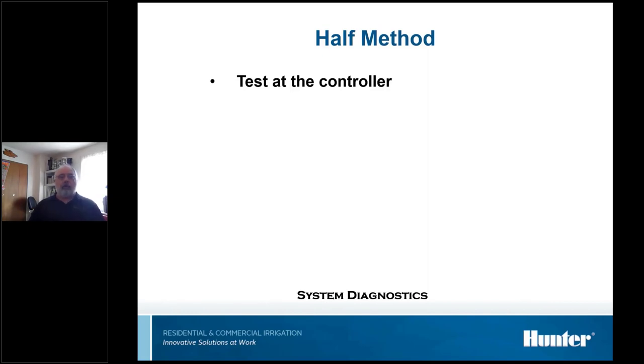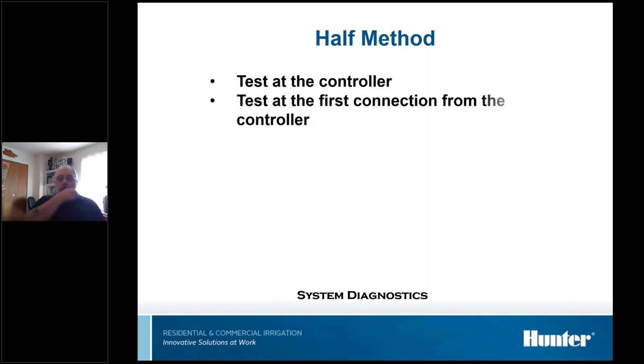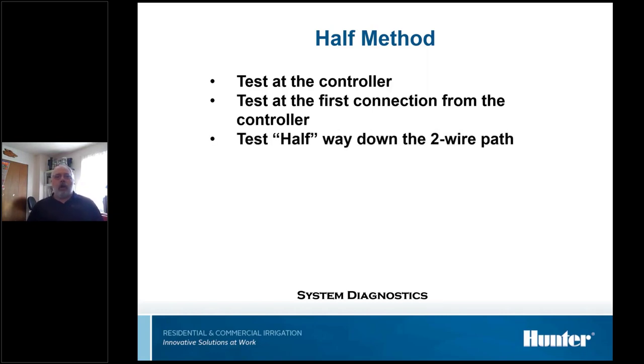Basically, we're going to check the controller, make sure the controller's working. Then we're going to go to the first connection outside of the controller and test there too. This is somewhat a reality check. I think I told you before, we see more problems at the first decoder in line than any other decoder. It's not like a high percentage, but then it makes sense to do it there. And then from there, we're going to start breaking this wire path into halves. We're going to go halfway out the wire path, disconnect the wire, and see what happens.